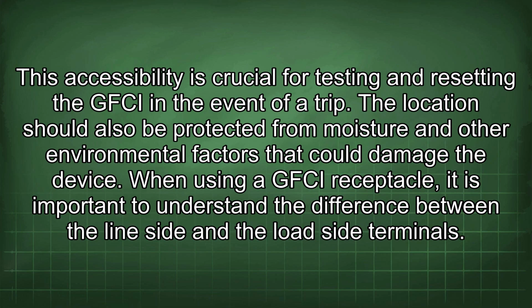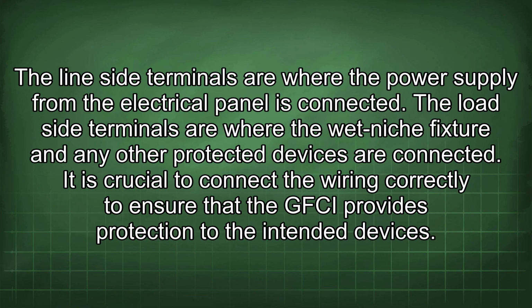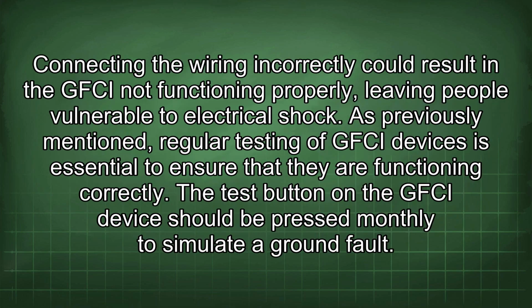When using a GFCI receptacle, it is important to understand the difference between the line-side and the load-side terminals. The line-side terminals are where the power supply from the electrical panel is connected. The load-side terminals are where the wet niche fixture and any other protected devices are connected. It is crucial to connect the wiring correctly to ensure that the GFCI provides protection to the intended devices. Connecting the wiring incorrectly could result in the GFCI not functioning properly, leaving people vulnerable to electrical shock.